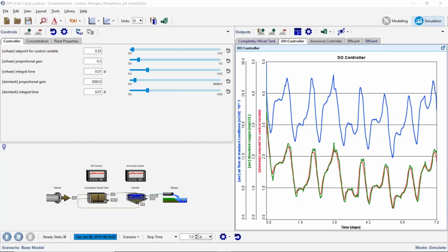Okay, so that was ABAC control. There are other variations that I've seen on this as well, where the signal for ammonia is taken from different places. You can even have different kinds of DO controllers. In the other webinar that I mentioned, we actually used an on-off controller, a high-low controller rather than a second PID loop here. That's also another variation that I've seen before. So it is a possibility to do whatever you like by combining the various types of controllers together.